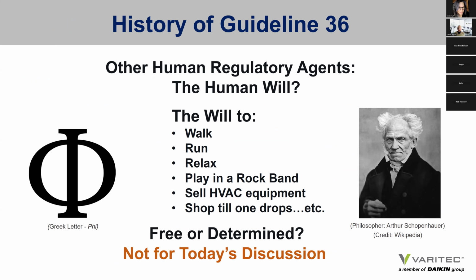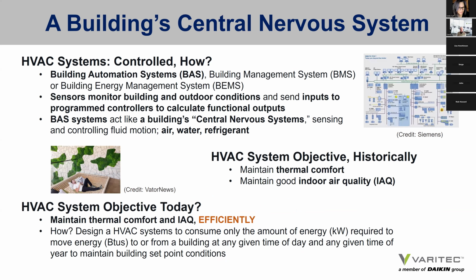There are other human regulatory agents like the human will, a fun topic to discuss. We won't have time today to do that, needless to say. But anyway, how are HVAC systems controlled? HVAC systems are controlled by a building automation system, also known as building management systems and building energy management systems. Sensors in a building monitor a building and the outdoor air conditions and send inputs to program controllers so the controllers can calculate and send out outputs. The BAS acts like a building's central nervous system, sensing and controlling fluid motion, air, water, and refrigerant, which are the heat transfer mediums in a building.